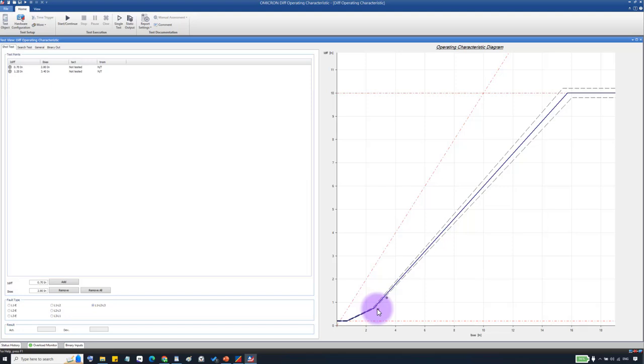It is needed because after injecting the value and after removing the signals, there are still some pickup and trip signals. If you check the relay log or the fault recorder, you can see this concept. If you remove all of the injection, there are still some pickup and trip signals. It is because the relay will keep these signals, like a pulse. For some time it should be injected.